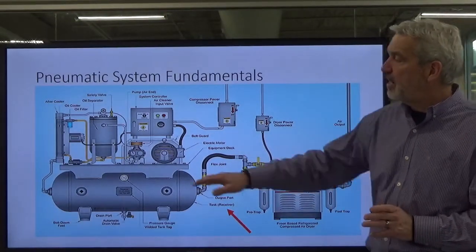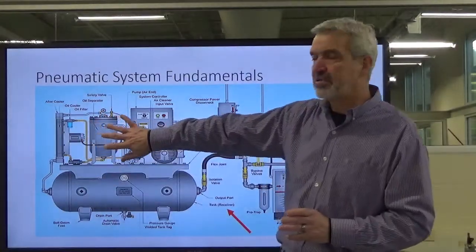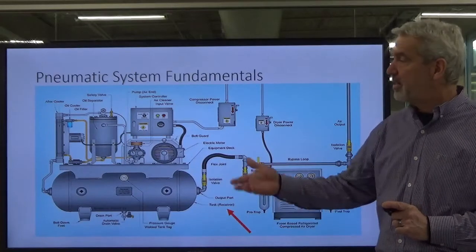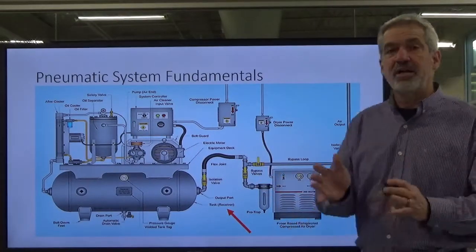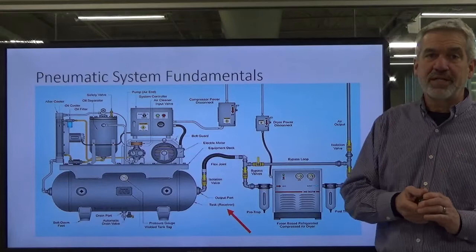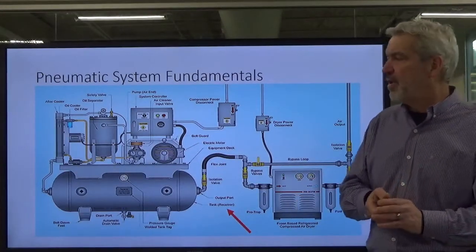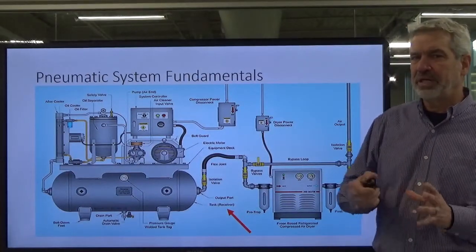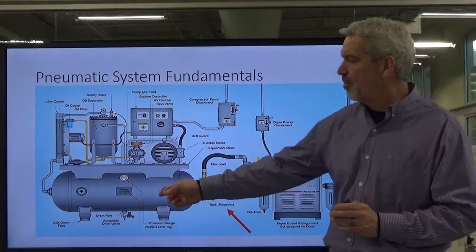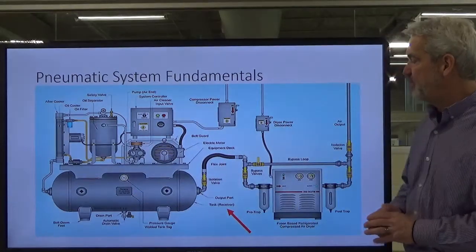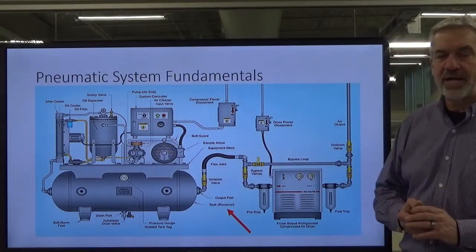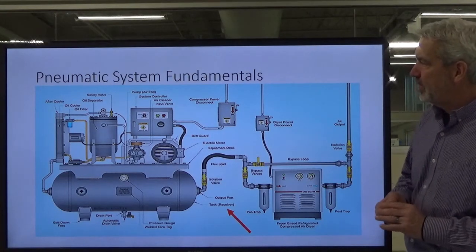And the thing about this is you can have pressure in here and this compressor not run at all. You might be able to do a few functions without it ever kicking on, with enough pressure in there. Not so with hydraulics. You'll never stroke anything. You'll have an accumulator pressure, but it won't have the volume that a receiver will. It can do a little bit, but you have a lot more energy packed into this receiver than you do typically for a hydraulic system. But that's it in its context, I should say. Anyway, that's just kind of a picture there.